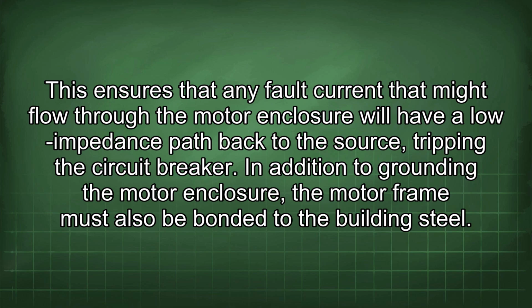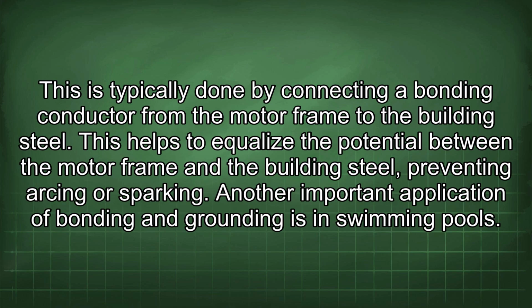In addition to grounding the motor enclosure, the motor frame must also be bonded to the building steel. This is typically done by connecting a bonding conductor from the motor frame to the building steel. This helps to equalize the potential between the motor frame and the building steel, preventing arcing or sparking.